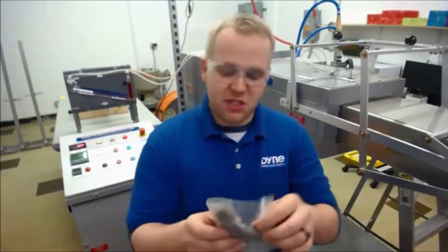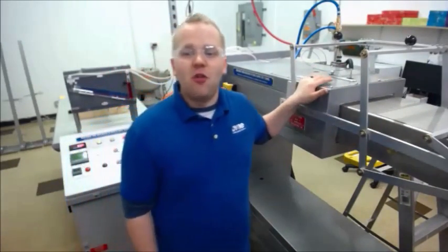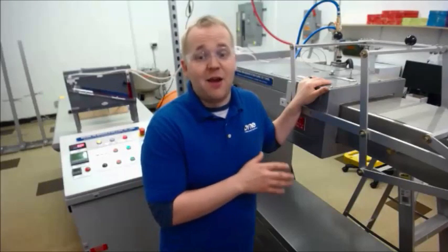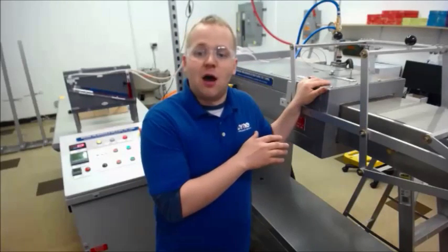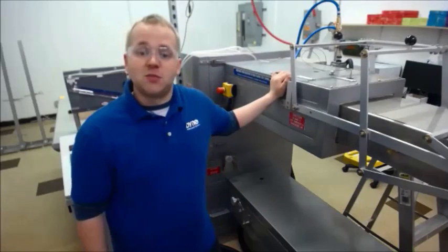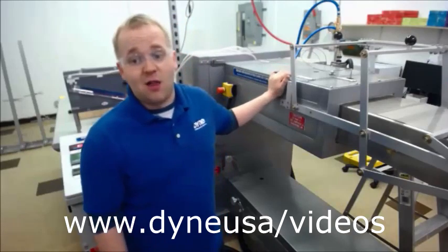The loading material I'll be using today is ordinary dust bunnies from home. We are running these heads at 275 degrees Fahrenheit — that's 135 degrees Celsius — with an airflow of about 2.5 meters per second. This environment is quite a bit lower than the listed temperature, so there should be no problem with these heads going off unless they are impaired in some way. The pressure I am applying is 5 psi, as called out in the appendix of NFPA 25. No water will be used for this testing. If you want to learn more about the machine I'll be using, our website has more information including a video on how it works.